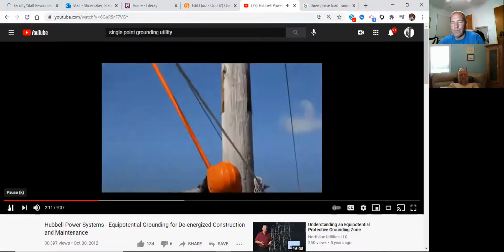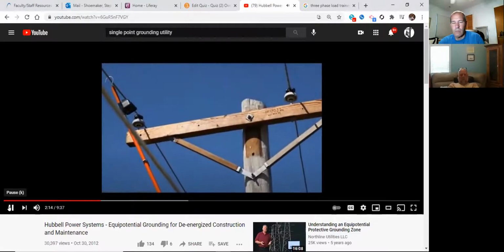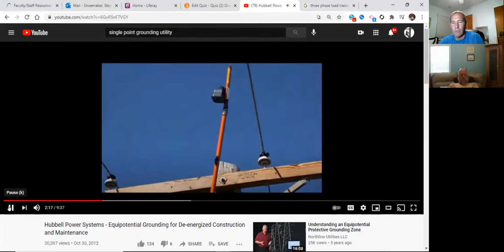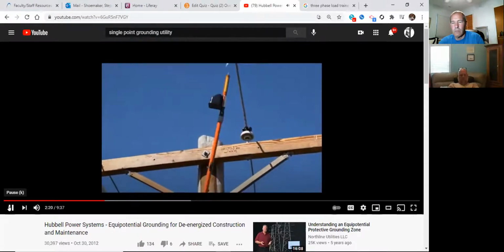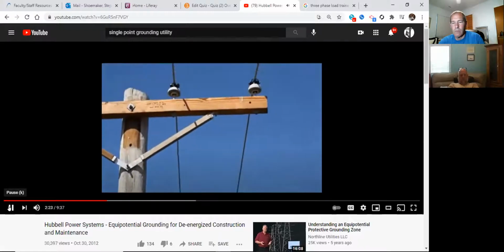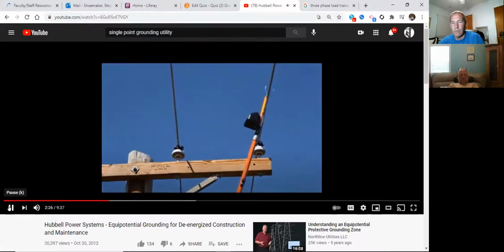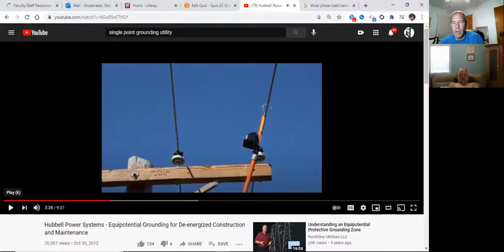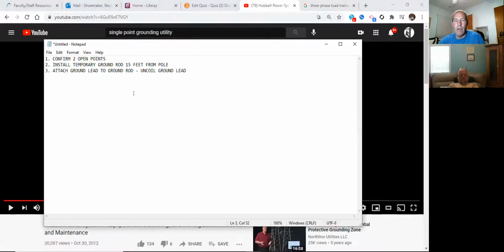Then the lineman tests each phase to make sure the line has been cleared. Notice that the unit is mounted on the hot stick to maintain proper clearance as though the line were energized. Okay, so step 4. Test for line voltage presence, P-R-E-S-E-N-C-E. Tick tracer or hot horn. We're just seeing if there's any voltage present.